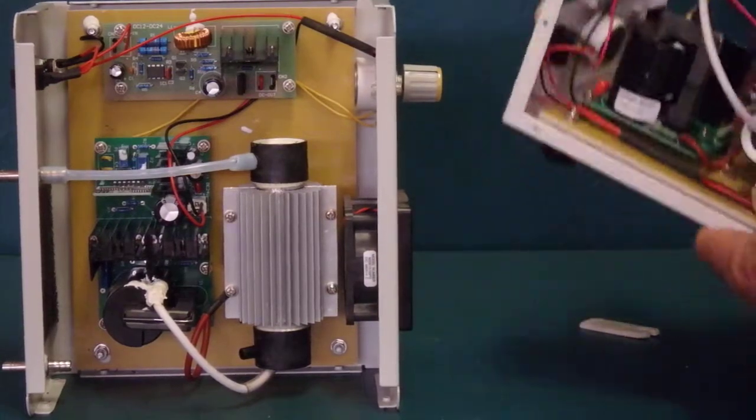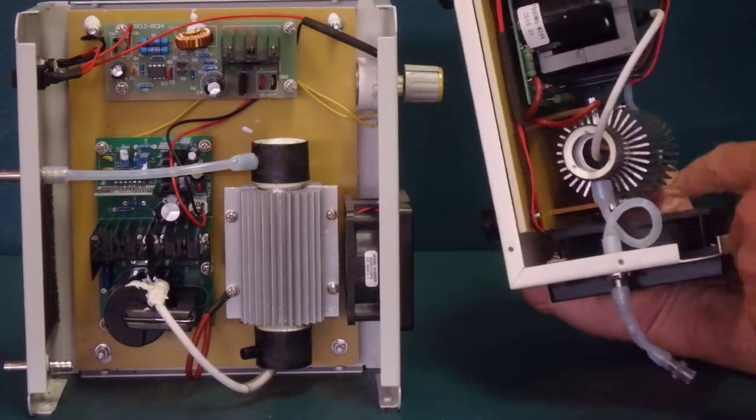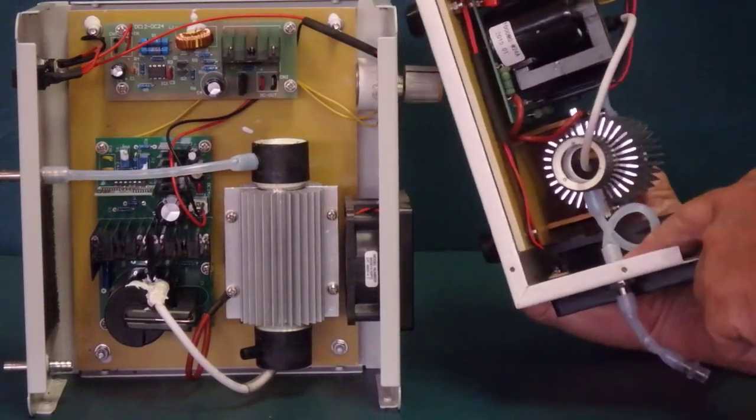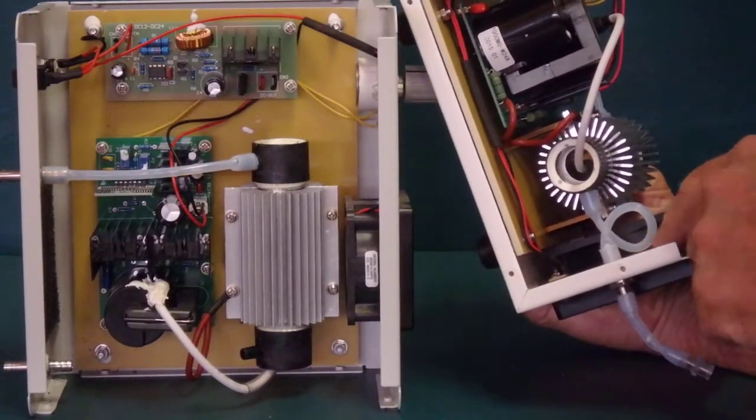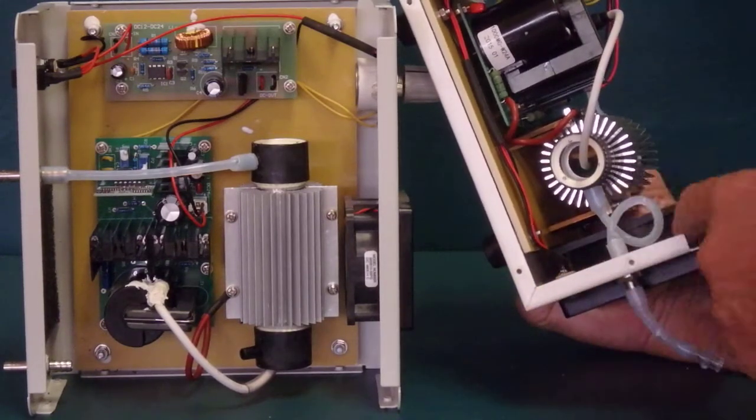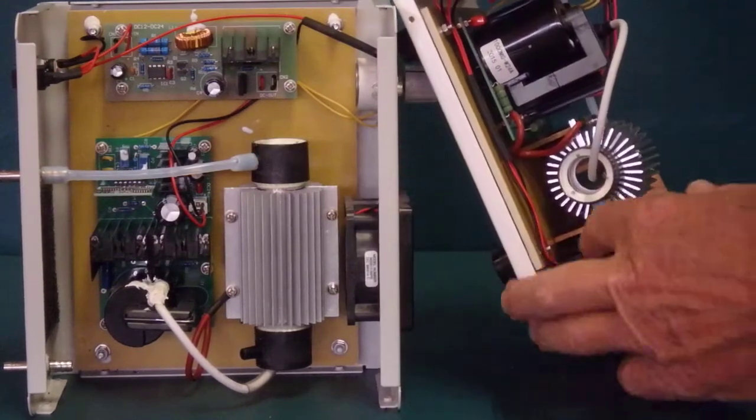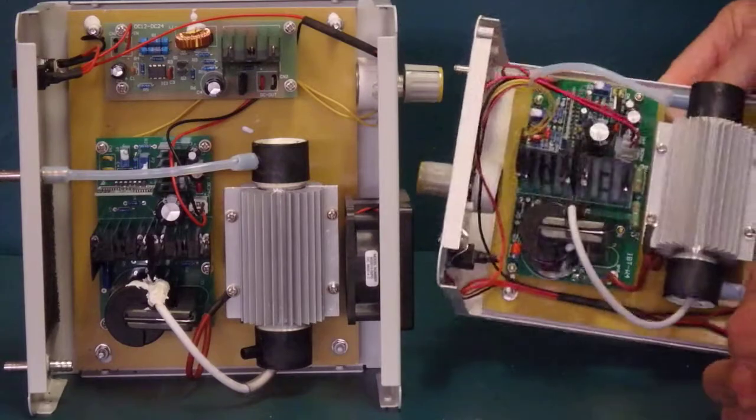On the ozone side, remember that short little segment that was in there that was very stressed. What we've done is replaced that short segment with a curve, a loop, that allows you the flexibility to maneuver the tubing around without stressing the tubing. We've got a tube here - again, this is all Teflon, the sleeve, just as we showed you before, to replace the tubing.